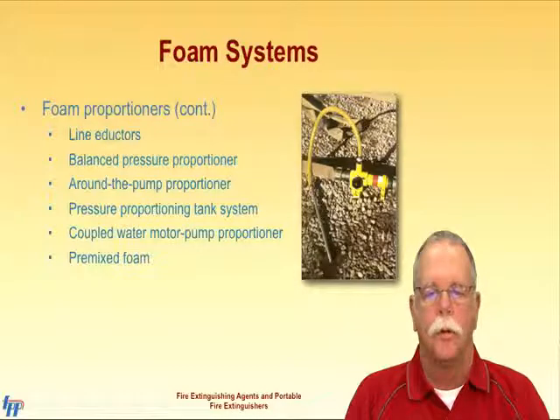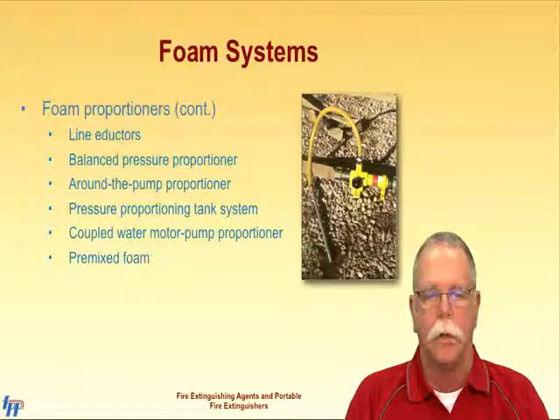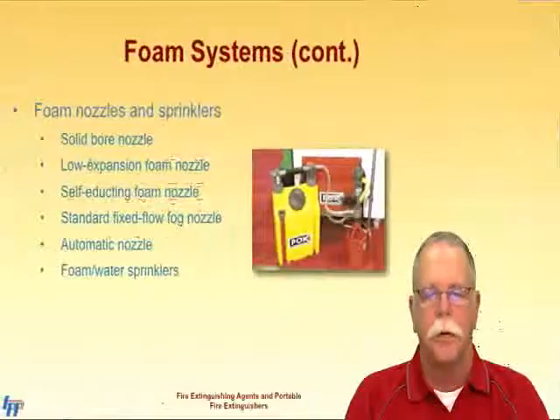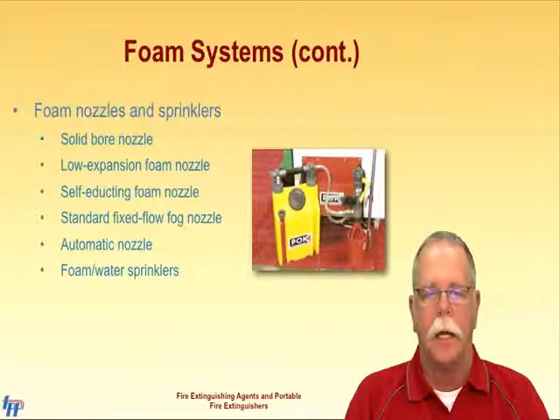Around the pump, proportioners use a proportioner below the foam tank to put foam into the water on the supply side of a fire pump. The foam is put in at a particular proportioning rate for a specific flow rate, and the pump is solely dedicated to foam operation. The pressure proportioning tank uses multiple tanks of foam concentrate. Water is pumped into the foam concentrate tanks between the tank and a bladder. The foam in this bladder is displaced by the water and is added to the discharge water.